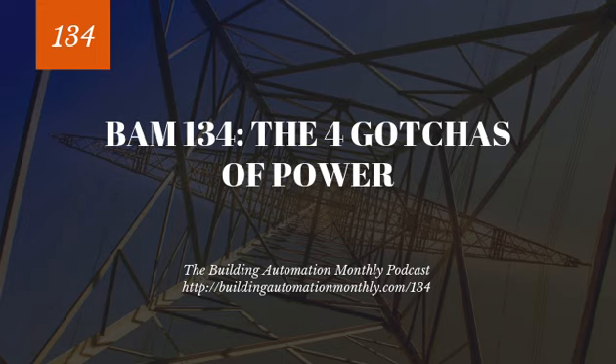When you talk through that example, you've got a control device and it needs power, and power is a loop. The power goes into the control device and returns back to the common. In some wiring instances, you need that common for the power to flow back to. In the past, a lot of what I would do is have power and common go to an actuator, and have voltage DC go to the actuator and come back to the voltage DC output common. That's how I would drive a 0 to 10 actuator.